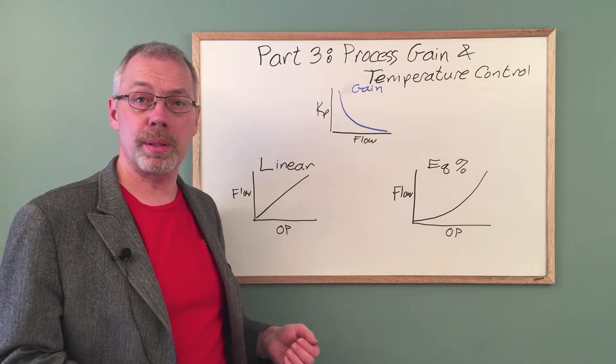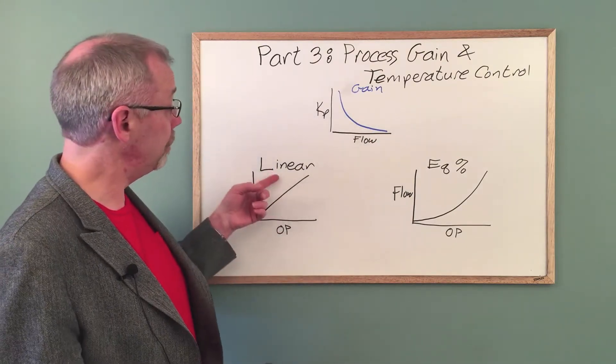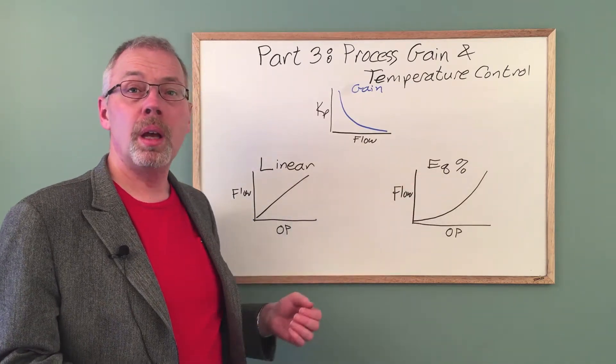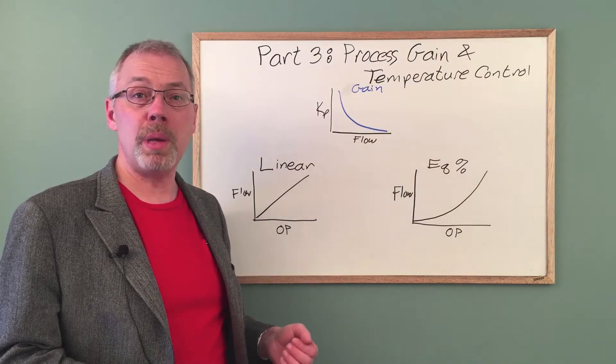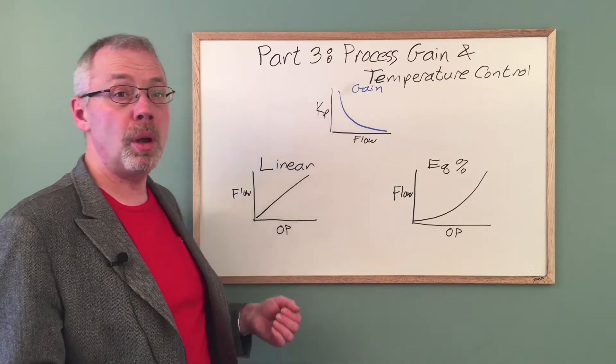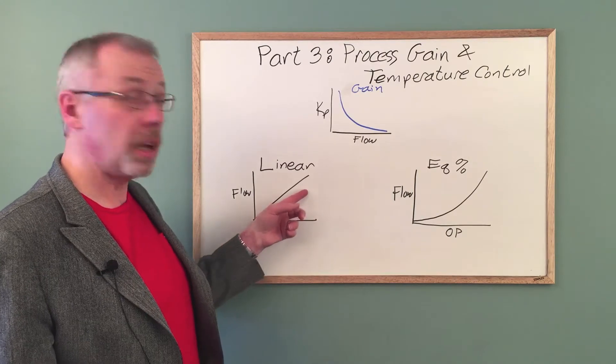There are two common control valve characteristics, a linear valve and an equal percent valve. A linear valve produces the same increase in flow rate for an additional 1% valve opening over the entire range of valve positions.